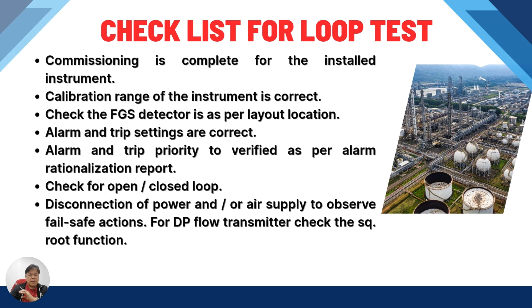Okay. So check for open and closed loop disconnections of power and air supply to observe fail-safe actions, because in our process line, guys, in our oil and gas industry refinery, we have a lot of air pressure. So we have a lot of air that pressurizes hydraulics in order to run our system, MOV, control valve, shutdown valve, etc., pressure transmitter, etc. Guys, that's the combination of our process, right? So DP, meaning differential transmitter, flow transmitter, check with a square root function, right? So this is a part of your checklist during the loop testing.